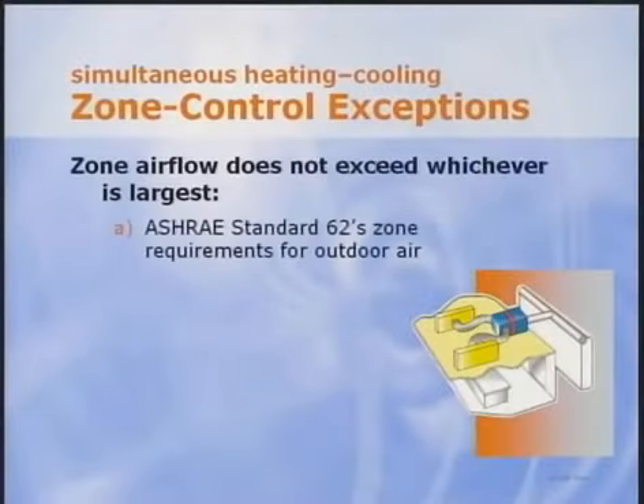Before reheating or recooling can be performed using new energy, the supply airflow in the zone must be reduced. By definition, a constant volume system cannot meet any of these exceptions, but many variable air volume systems can be designed and operated to comply with one of the airflow limits allowed by this standard. Let's look first at exception A, setting the zone airflow to the required ventilation airflow. Considering the requirements of Standard 62.1 on a VAV system, this will require bringing in 100% outdoor air when any zone closes to this minimum.